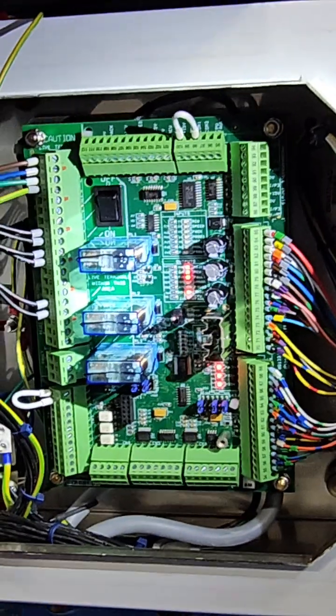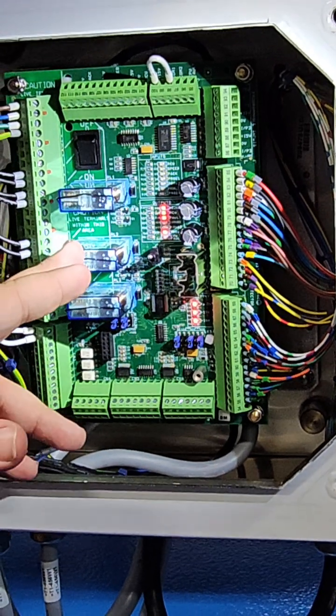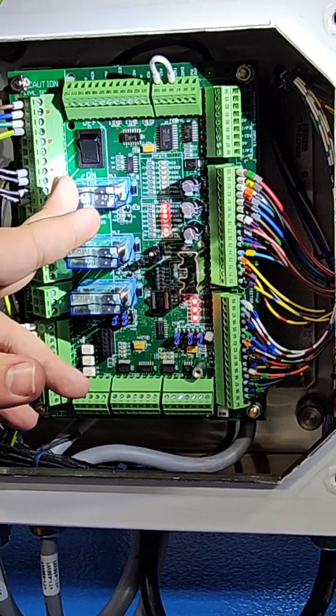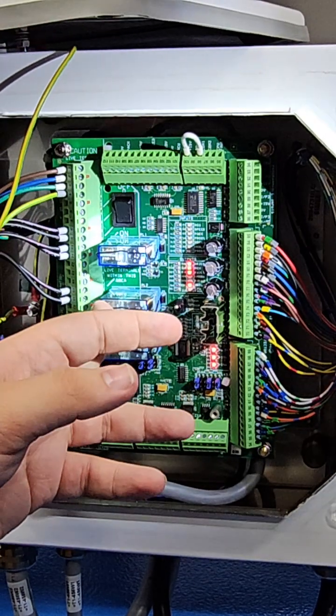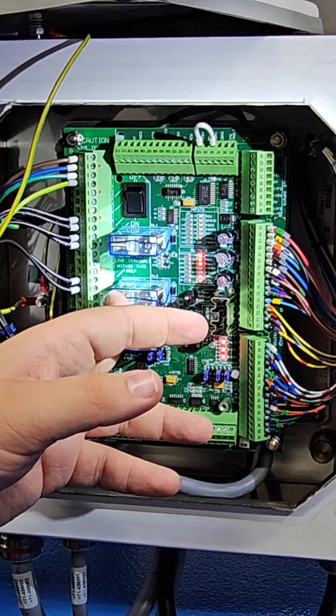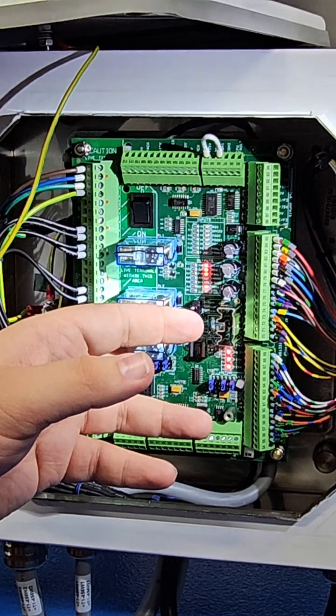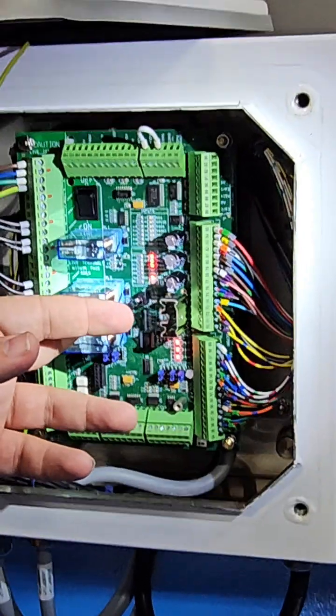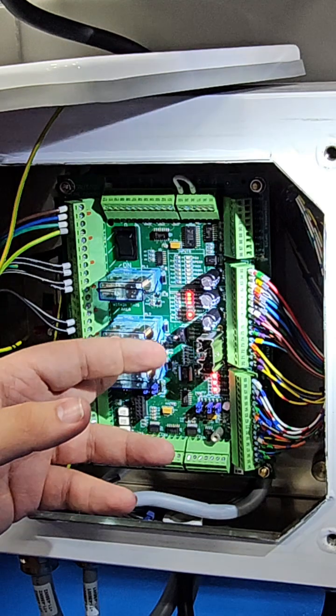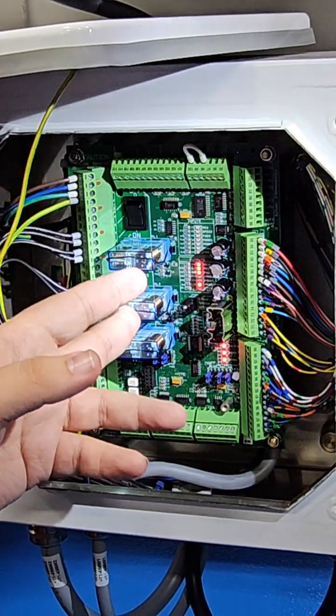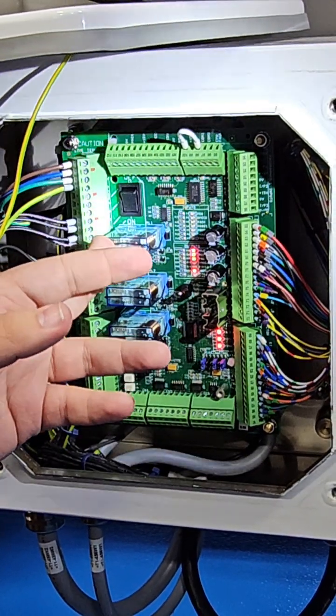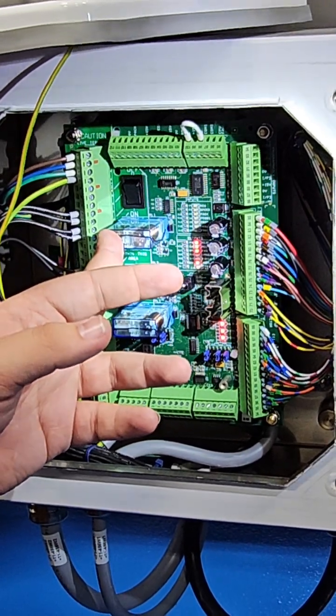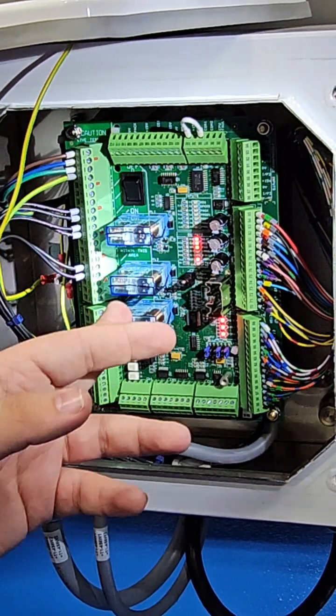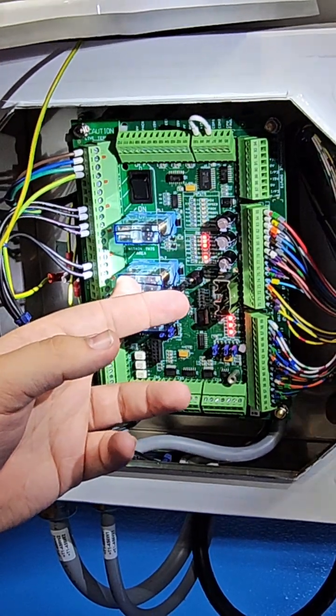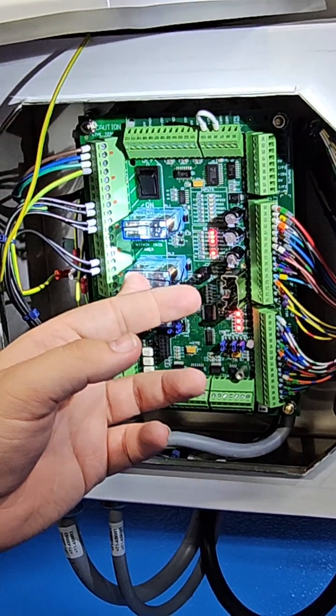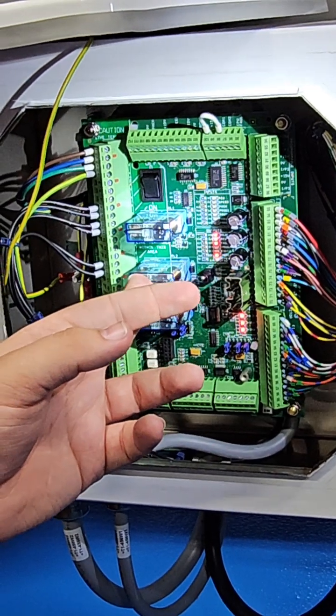That's important, because if this doesn't go over — let's say the system is saying reject, but the arm isn't moving, let's say we lost air — if this isn't working and that reject isn't going, it doesn't matter how good the metal detector sees the metal, contaminants are going down the line. You check this relay by passing a piece of metal and holding your finger on it, and if it clicks, you know you're good. To check the other one, you cycle the rejector, and it should click every time the reject cycles. Pretty straightforward.